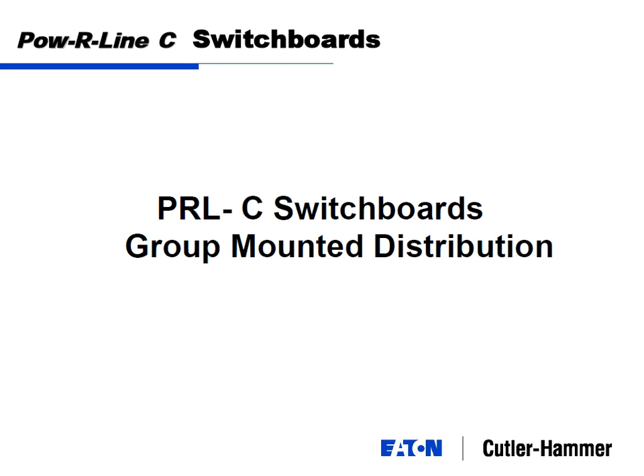Do you have anything that does that at the circuit level or strictly at the main? That's a good question. We don't have anything that monitors directly at the circuit level for 20 amp type circuits. We have it at the circuit level for the 3-pole breakers. So, 100 amp circuits is kind of what I would say. And usually that's dictated by cost effectiveness. If you're going to spend $500 on a point to measure a 20 amp breaker, and you can run that breaker for 100 years, and no matter how much monitoring you do, you'll never be able to save $500 in energy. So we kind of looked at it that way.